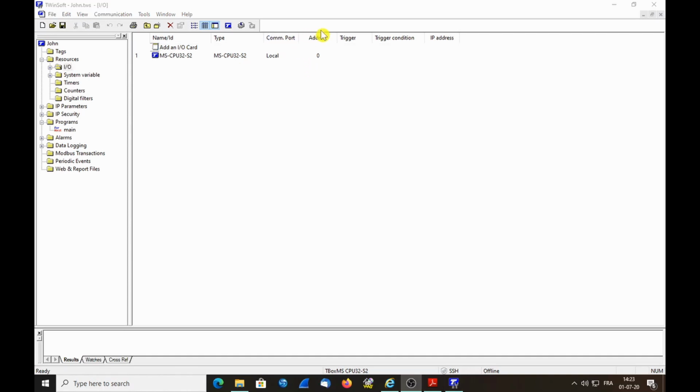Each module has a software address which corresponds to the slot ID in which it is inserted. There is one exception to this: the CPU. The CPU can be placed on two slots, slot 0 and slot 1. This is because we support T-Box redundancy, meaning we insert two CPUs on the rack, and these will be on slot 0 and slot 1.